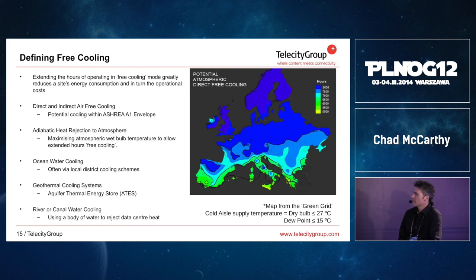The diagram on the right-hand side is from the Green Grid, which is an organization which we do support. It talks about direct free cooling. Free cooling is a term which people normally associate with the atmospheric temperature, rejecting the heat from the data center to the atmosphere. It doesn't have to be to the atmosphere. Direct free cooling means that you effectively take the cold air from outside, put it into the data center, take the warm air from the data center and put it outside.